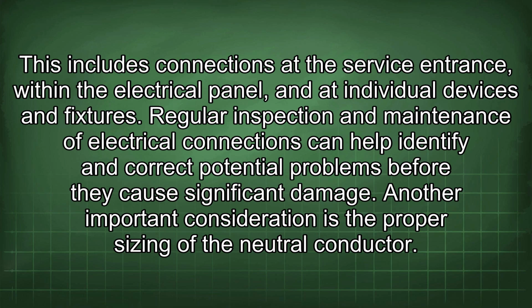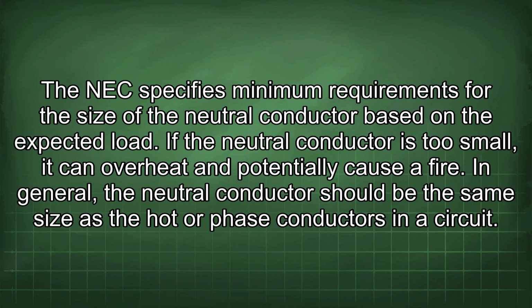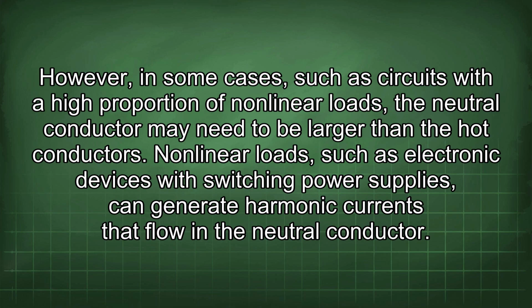Another important consideration is the proper sizing of the neutral conductor. The NEC specifies minimum requirements for the size of the neutral conductor based on the expected load. If the neutral conductor is too small, it can overheat and potentially cause a fire. In general, the neutral conductor should be the same size as the hot or phase conductors in a circuit. However, in some cases, such as circuits with a high proportion of nonlinear loads, the neutral conductor may need to be larger than the hot conductors.